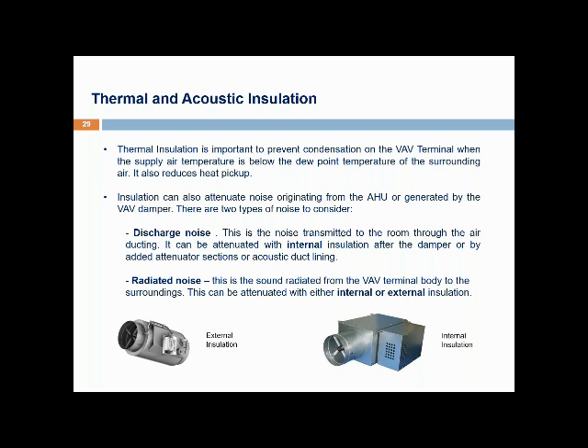Most VAV terminals have some form of insulation serving two purposes. First, to thermally insulate the unit — particularly to prevent condensation on the unit casing if the temperature of the supply air inside the terminal is lower than the dew point temperature of the surrounding air. Just as a glass of cold water will quickly get covered in condensation when the glass temperature is below the dew point, the same happens with a VAV terminal. We often insulate purely for that reason.